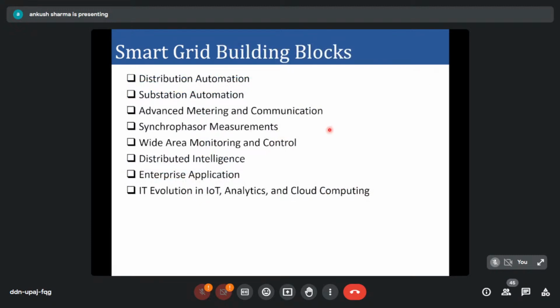What are the different building blocks we see in the smart distribution system? First is distribution automation. We started our journey with distribution automation, where small automation activities like relay operation and breaker automation took place. Then later we switched over to substation automation, where we added intelligent electronic devices. We made the substation IEC 61850 enabled, where every aspect of substation operation is automated, and almost in real time the operation can take place with the help of substation automation.